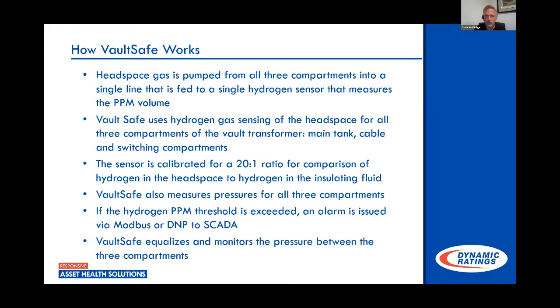However, another problem you'll run into with this is you may have leaks on that transformer. So if you have leaks, now you have hydrogen escaping the atmosphere, which is where its natural state is. So that even prolongs that time to pick up the monitor even further out, because you're not getting that equilibrium due to the escape to atmosphere that you're seeing of hydrogen. And if leaks bad enough, you may not ever see it, because again, especially if it's a PD event where you're generating quickly, if it's generated in a gaseous state, that's going to go straight to the compartment, and then you do have to wait for that saturation back into the oil. So that was kind of the thought process around putting the monitoring together.